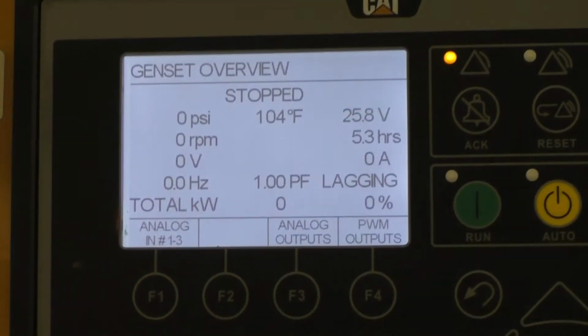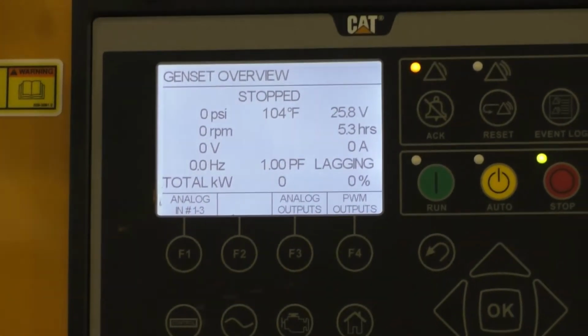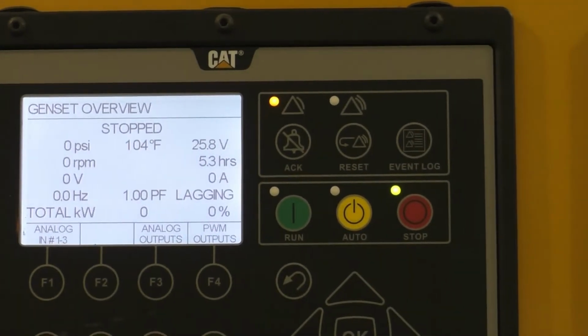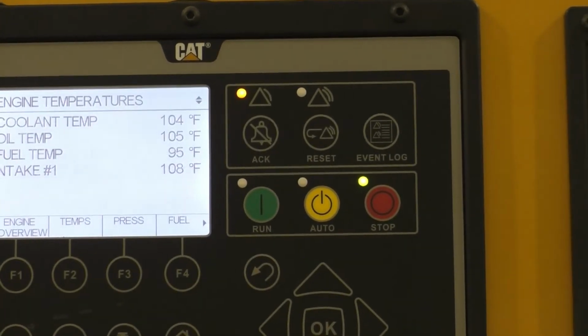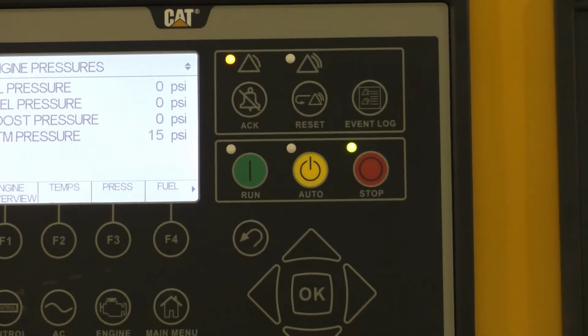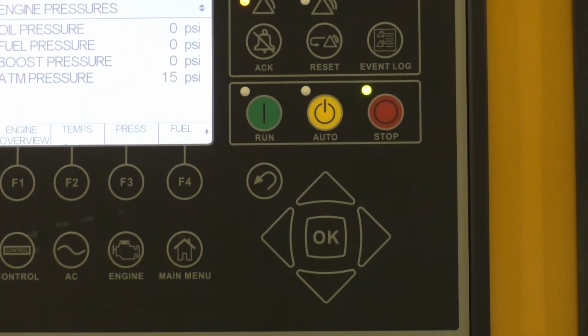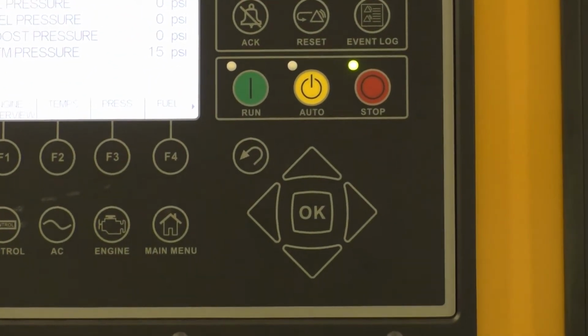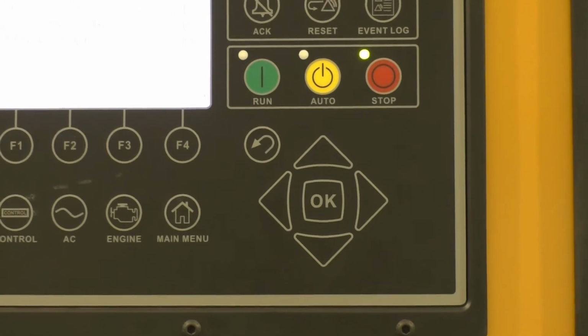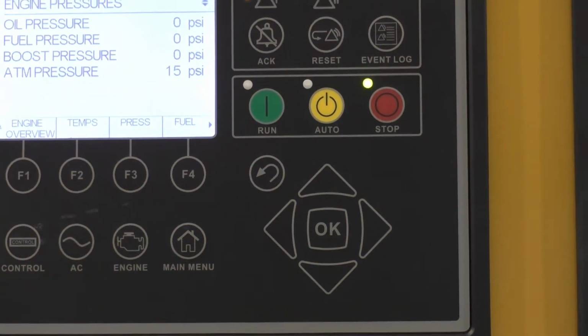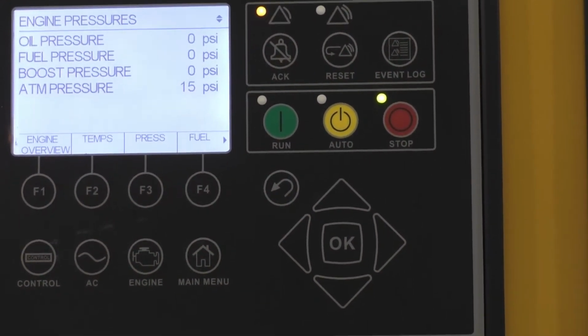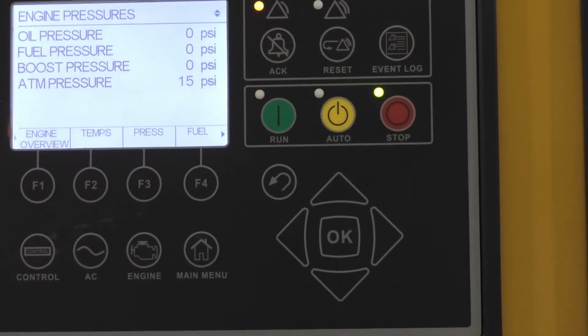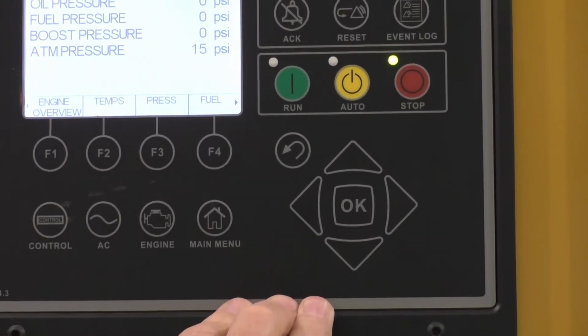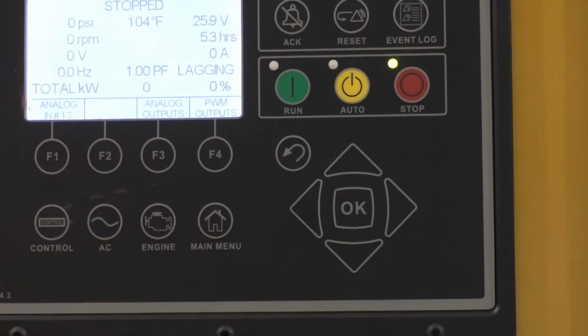What's the 0 PSI upper left? Oil pressure. If it's not running, would it have any? It doesn't tell you fuel pressure unless you go to the engine, and then you start going down, and you'll find here. Okay, there it is. Yeah, but you wouldn't have fuel pressure unless it's running either, because they're mechanical pumps. Oh, okay. Not electric. Yeah. Well, I mean, there is actually an electric pump for bleeding the fuel system. It's a purge, but it's not running unless you call for it to run. But again, that's the one I use 90% of the time.